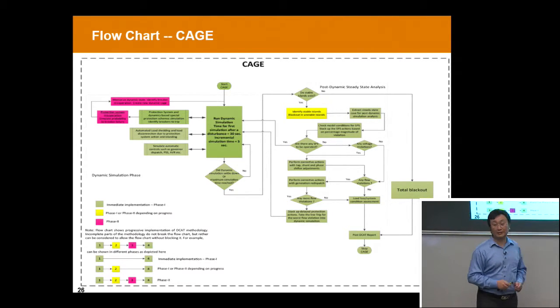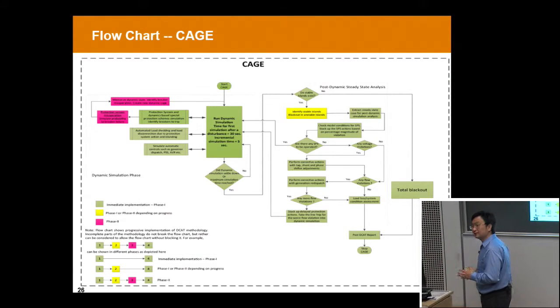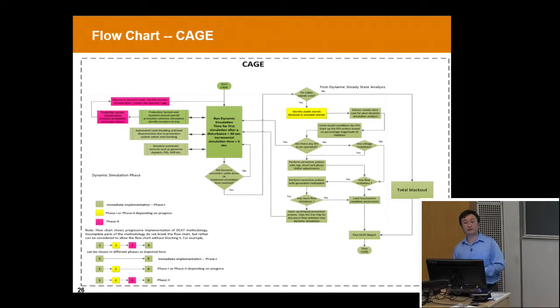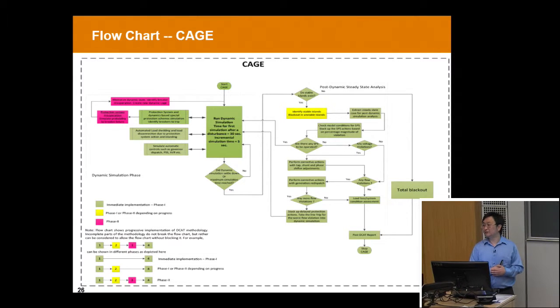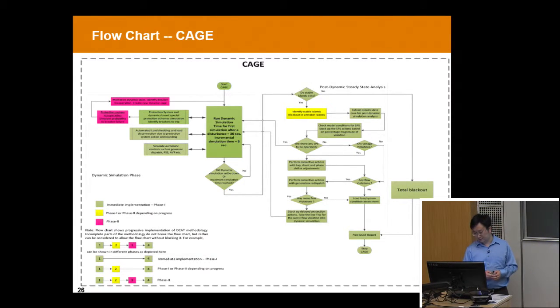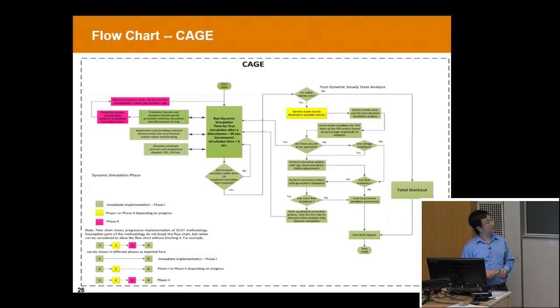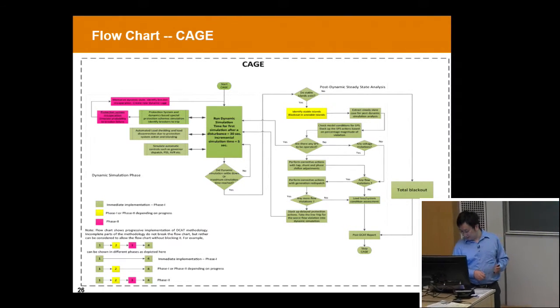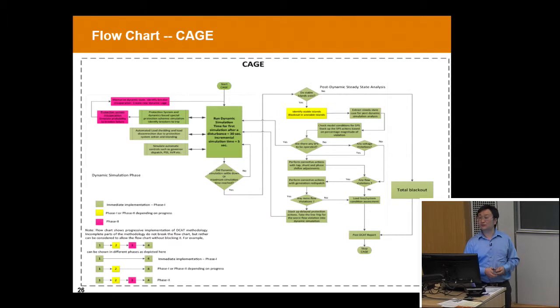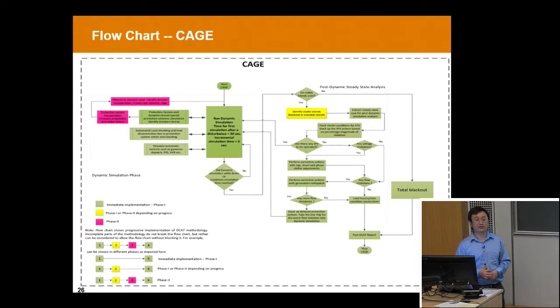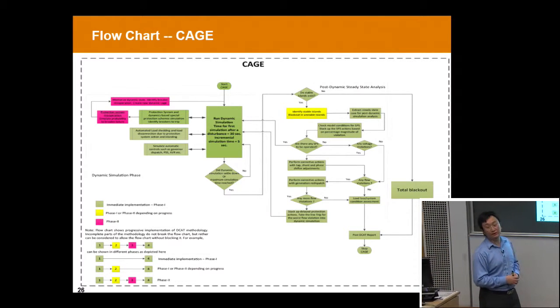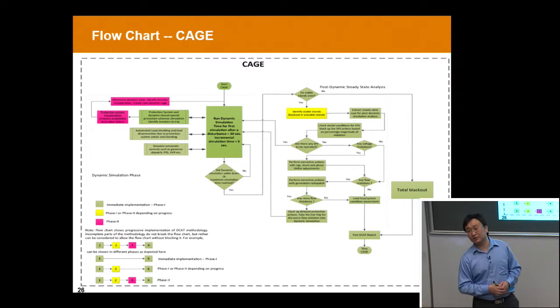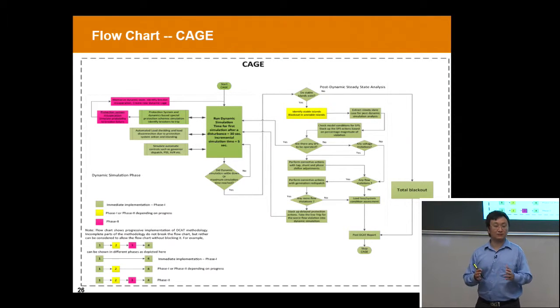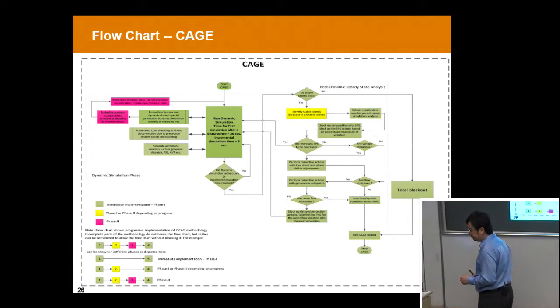Then we check system behavior under the new steady state. If there are any violations, we want to capture those unmodeled processes from the dynamic simulation here, especially longer-term actions like transformer tap ratio changes or overcurrent protection relays tripping lines. These normally take 30 minutes or even longer, but dynamic simulation typically takes 30 seconds up to a minute to run.